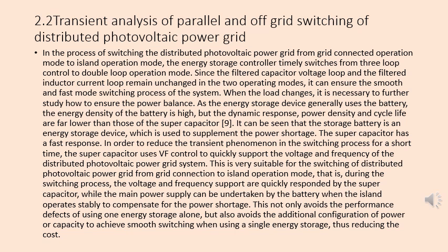In order to reduce the transient phenomenon in the switching process for a short time, the supercapacitor uses VF control to quickly support the voltage and frequency of the distributed photovoltaic power grid system. This is very suitable for the switching of distributed photovoltaic power grid from grid connection to island operation mode. That is, during the switching process, the voltage and frequency support are quickly responded by the supercapacitor, while the main power supply can be undertaken by the battery when the island operates stably to compensate for the power shortage.